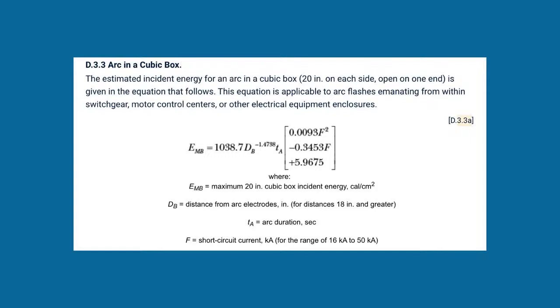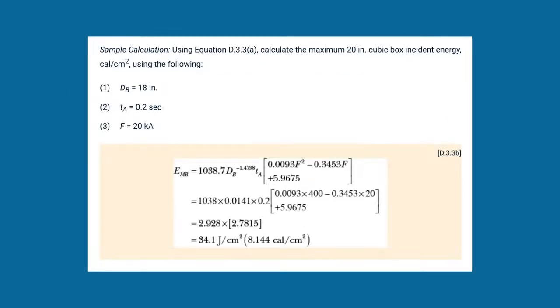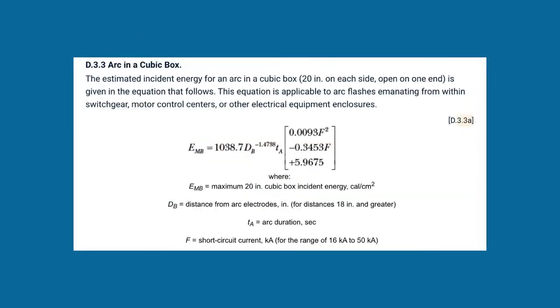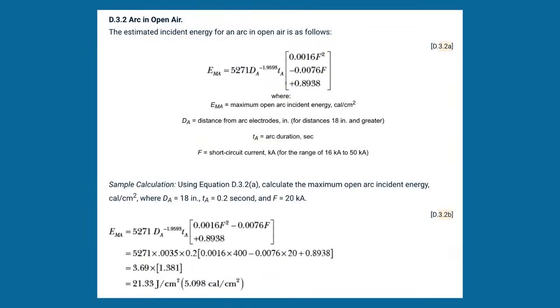Then they've got your DB, which is the distance from the electrodes. You've got your TA, which is your arc in seconds. And then your F, of course, is your short circuit current. All right? Now, here's the calculation. What I want to point out, let me go back here because I want you to see this. We've got my distance from the electrodes, 18 inches, my clearing time's 0.2, and my short circuit current's 20 kA. We just did that for an arc in open air and got 5.098 cal.